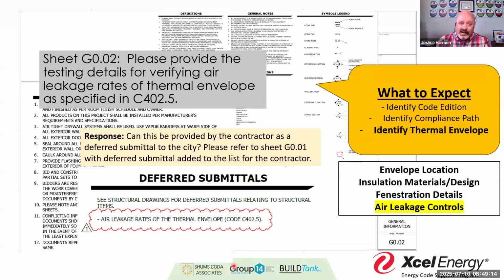And in that particular design, they were really close to being within that 10 to 15% of compliance, expecting that all the air in the volume of that building was going to stay there for a more significant amount of time, versus the traditional architectural designer coming in saying, well, it's going to leak. We're going to see air changes double what the mechanical designers are thinking. So that equipment's going to run longer or run more than was intended. So when you come back and make these cost benefit calculations, that equipment's going to run more than it needed to because the envelope wasn't as secure as we wanted it.